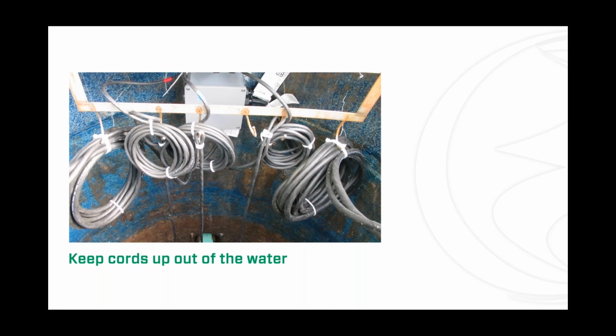You can't imagine how many times we get a pump back here and find the problem is that it got a hold of the pump power cord. Sorry, that's not a warranty situation - that's an installation error, not a manufacturing defect. So again, these J-hooks are great, and I'd highly recommend using them. Even if you have an additional float bracket or pole system that your floats are tethered on, use these J-hooks. They're a great way to keep your cords, your floats, even your pull cables or ropes tied to your pump - a great place to put all those things.